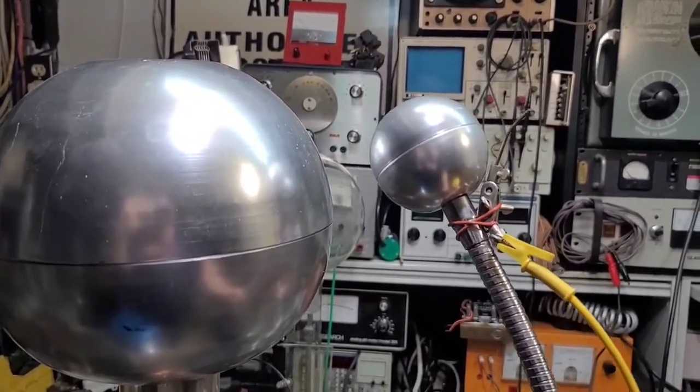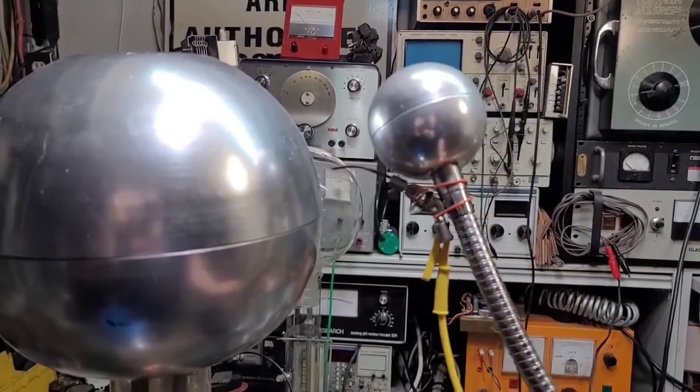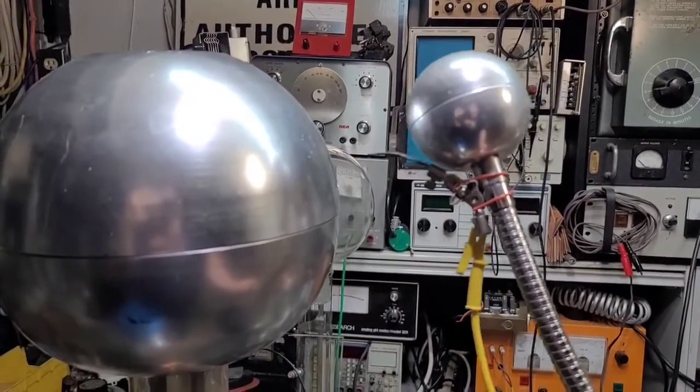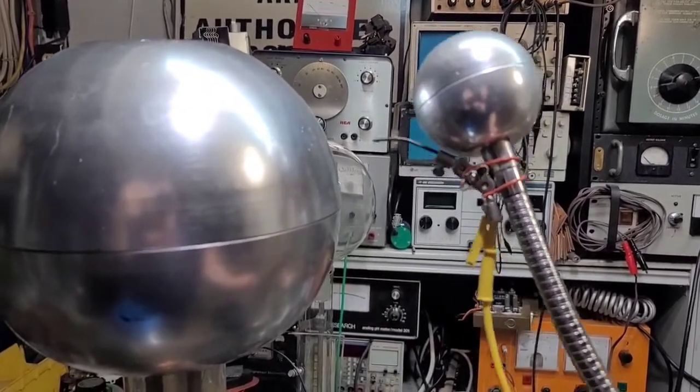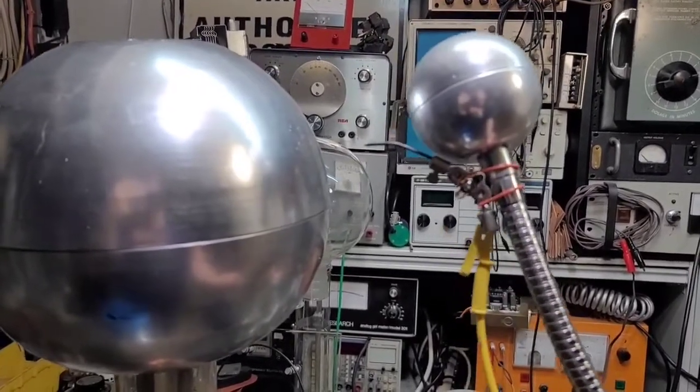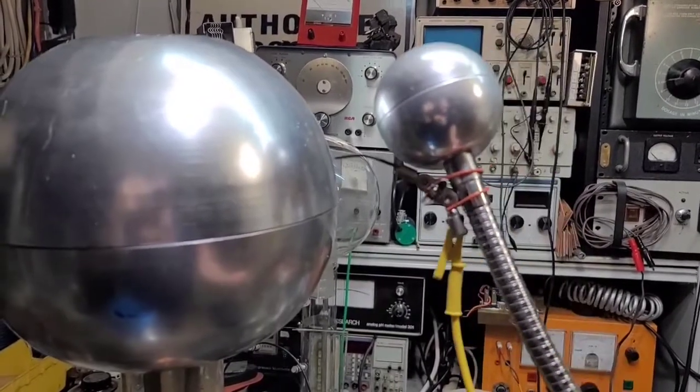Instead, you put lightning rods on the building like this point here. This point allows the electrons to concentrate at the tip and they bleed off the bigger charges, kind of like poking a small hole in a balloon instead of popping it. You're bleeding off that pressure very controlled in a very small manner.